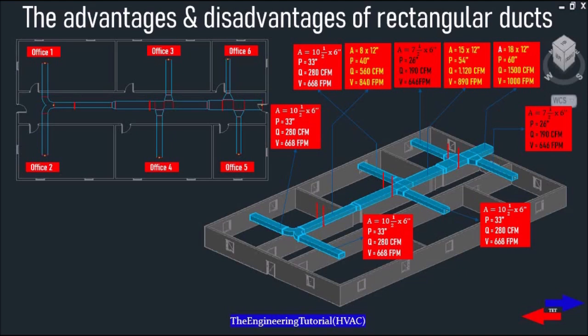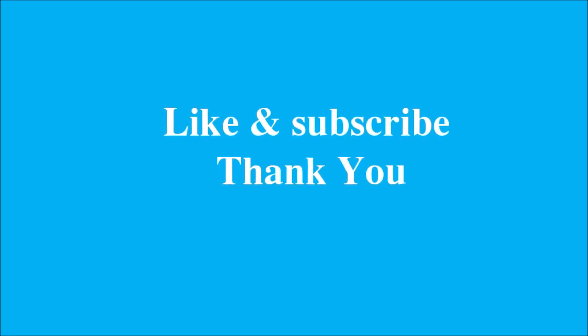The larger perimeter also means more air will come into contact with the material, adding friction to the system. Friction in a system means the fan needs to work harder, resulting in higher operating costs. Therefore, always use round ducts whenever you've got enough space, and use rectangular ducts whenever you've got tight or limited space. That's it for today — I appreciate you for watching this video. I'll see you next time.